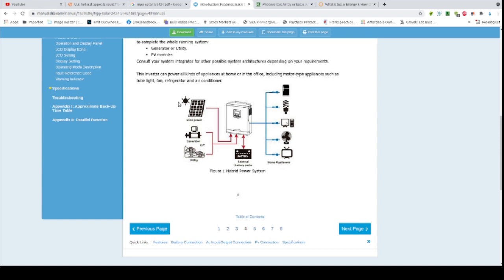And then you have your solar panel power array, and that can be 30 to 80 volts DC. So you can take 4, 100 watt 12 volt panels and put them in series, and since the raw voltage of a 12 volt DC solar panel is approximately anywhere from 17 to 20 volts, you're going to meet that 80 volt requirement. And another thing too, when you put solar panels in series, it doesn't increase the current.